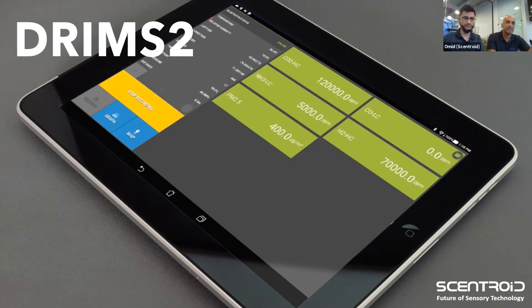It interfaces with the GD600, which is a dilution device, and you can calibrate by applying certified calibration gases from a cylinder. The GD600 will administer the gas to the system and collect the information, so you can do a full span calibration using that product.